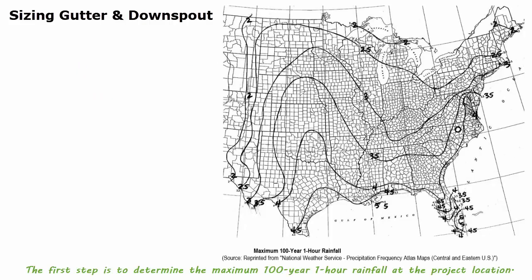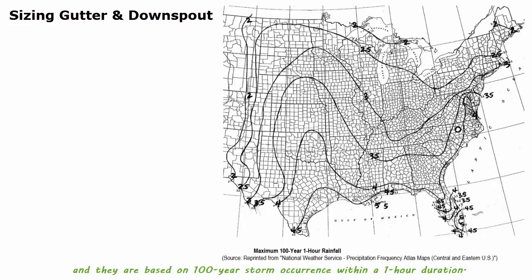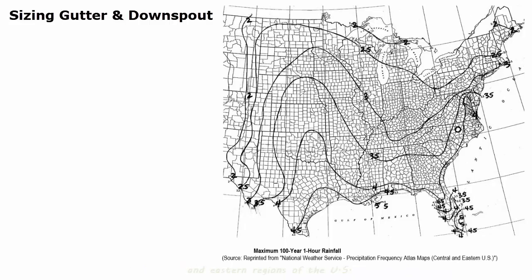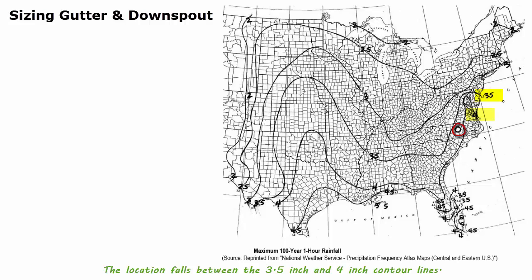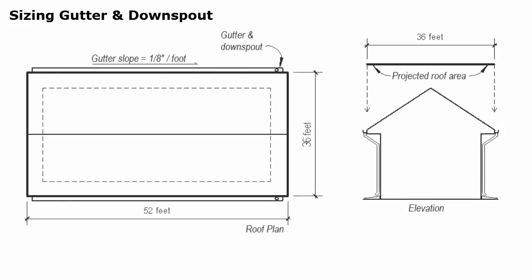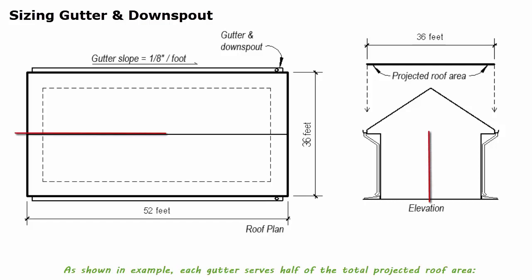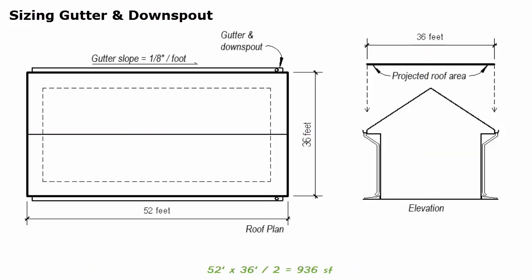The first step is to determine the maximum 100-year, one-hour rainfall at the project location. Design rainfall rates are established by the US Weather Bureau based on 100-year storm occurrence within one-hour duration. This map shows the maximum 100-year, one-hour rainfall for the central and eastern US. Raleigh, North Carolina is located in Wake County; the location falls between the 3.5-inch and 4-inch contour lines, so 4 inches is selected to represent the worst-case scenario. The second step is to calculate the projected roof area for each gutter; each gutter serves half of the total projected area, which is 52 times 36 divided by 2, equaling 936 square feet.